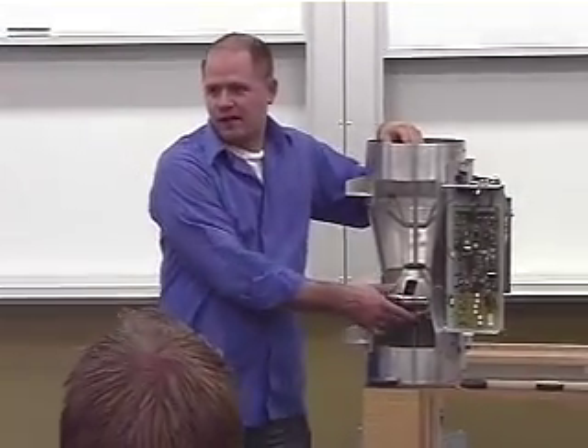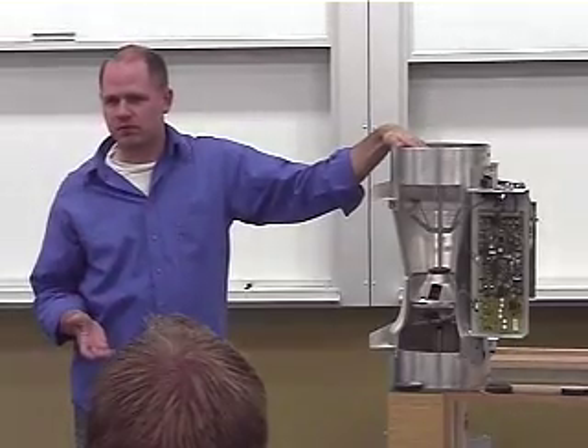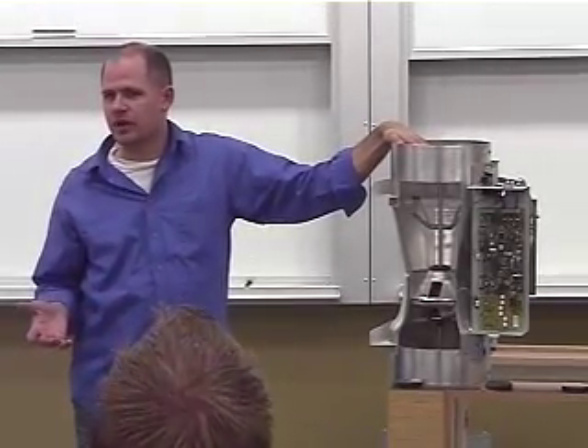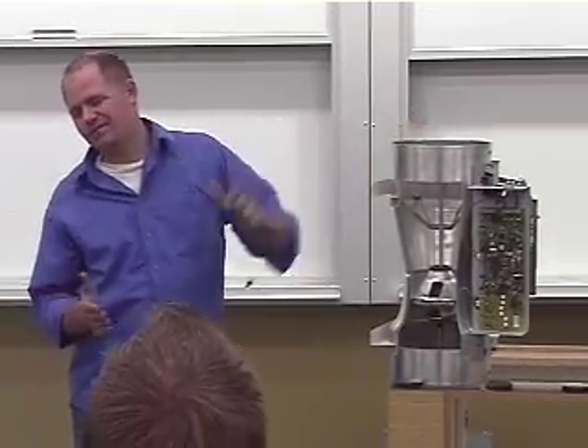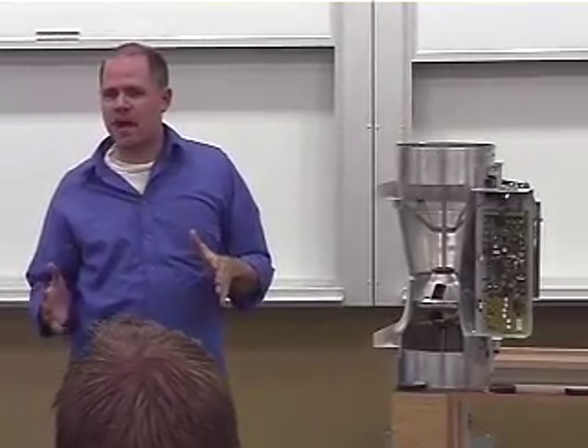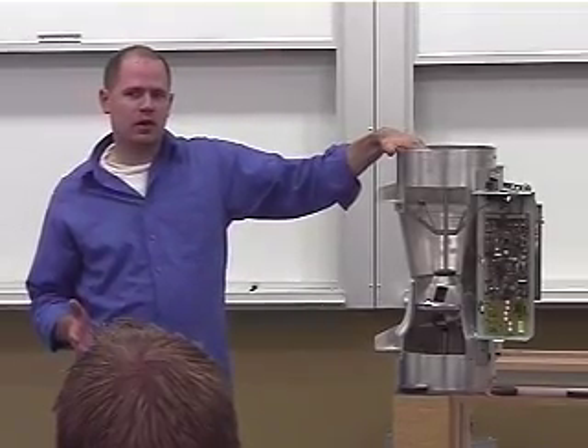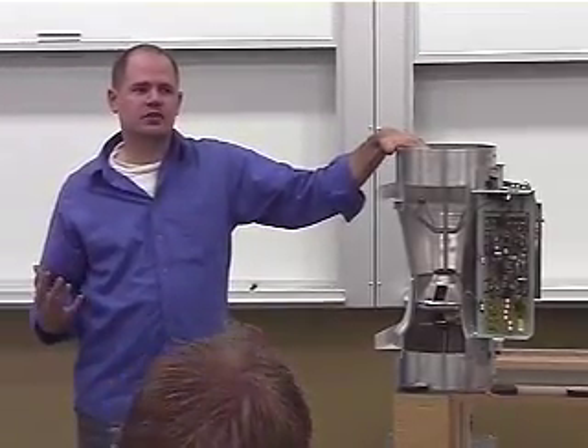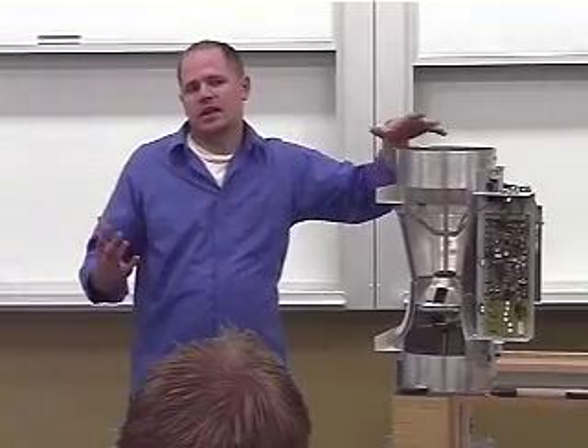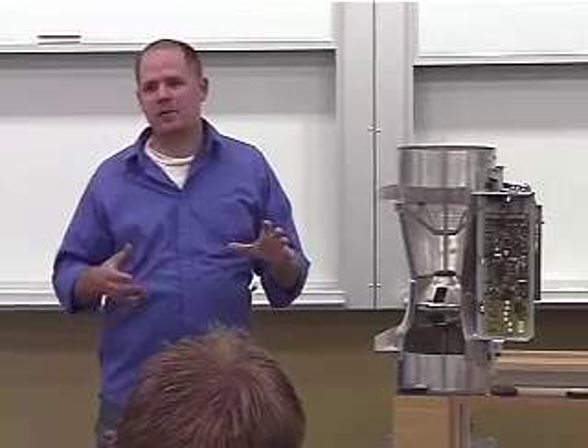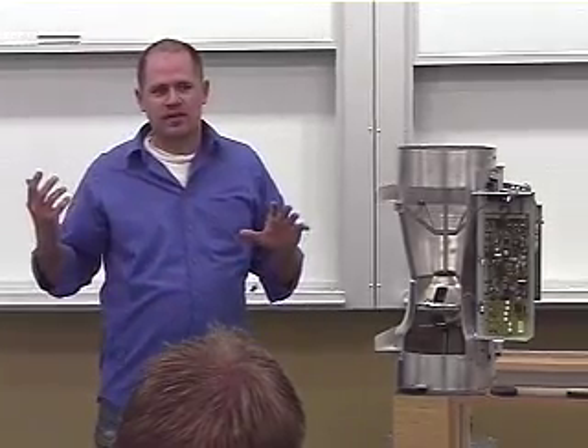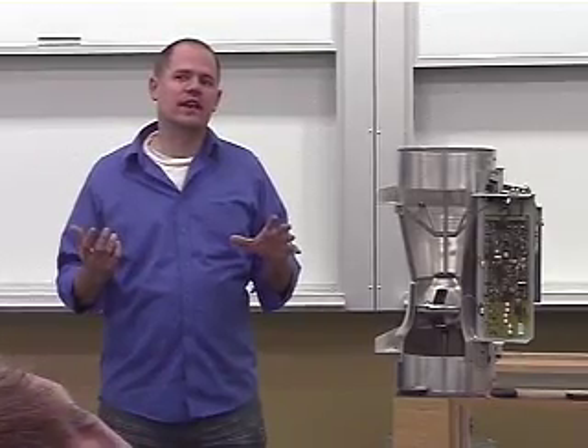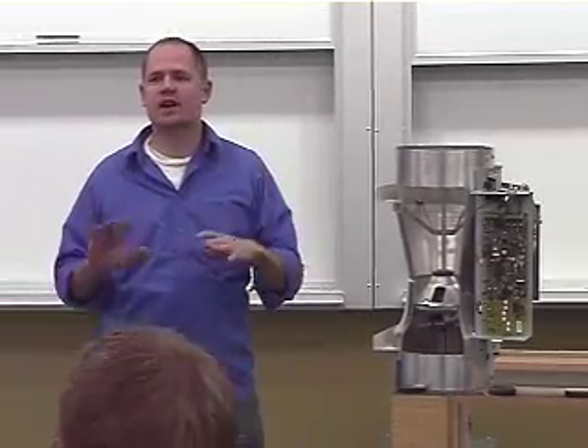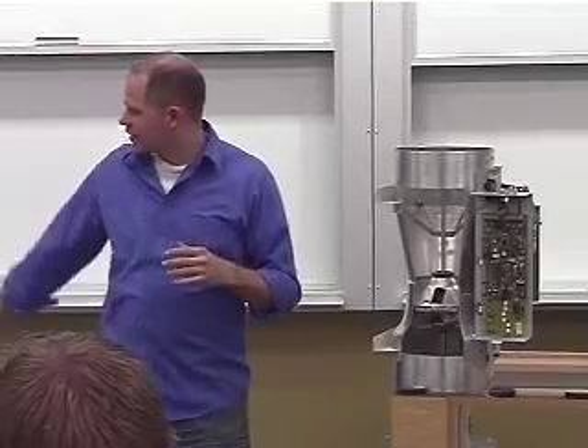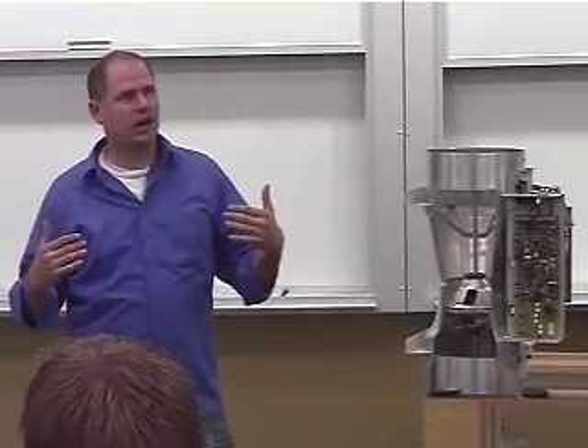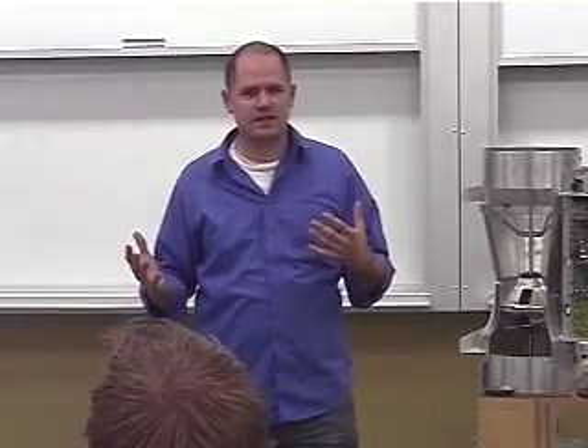From the factory, these have a maximum and minimum level that they are set up to based off the design flow numbers. Those can be pushed a little bit. Typically those are set up in balancing. The way these control a room overall is through offset control. An offset is where you keep track of how much air you're pushing in the room and how much air you're pulling out. That number is the equivalent to the air that's being pulled or pushed out of the room through other areas. So typically that's under doors, around edges of doors, basically any leaks in the walls, those kind of things.